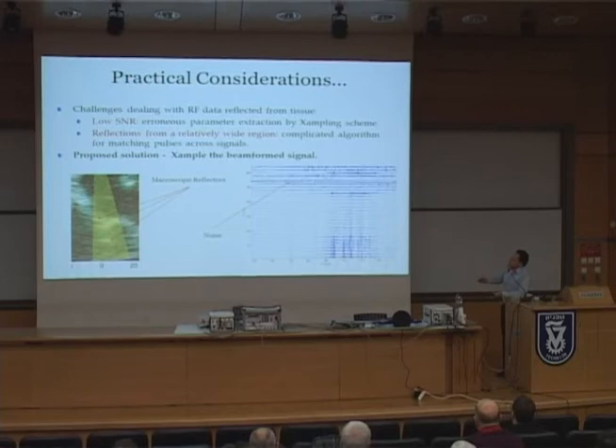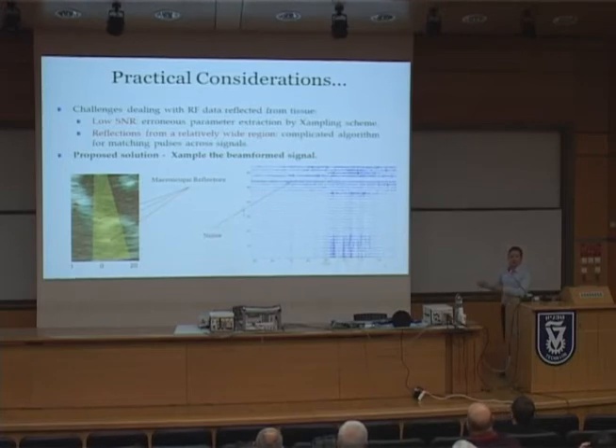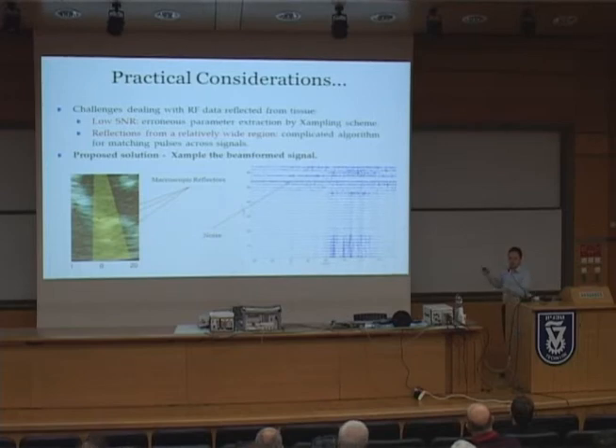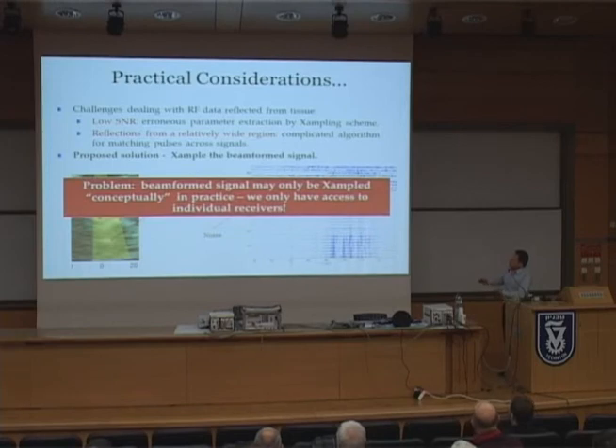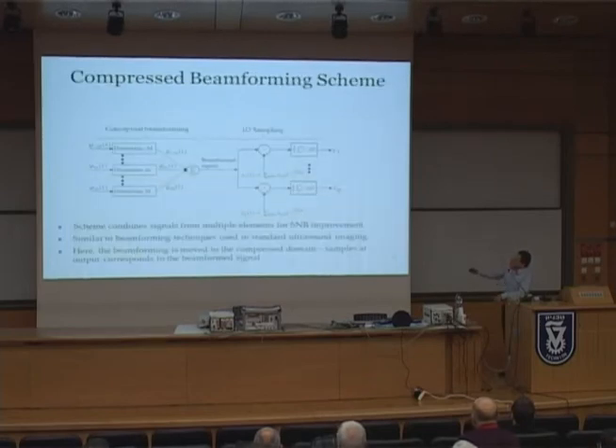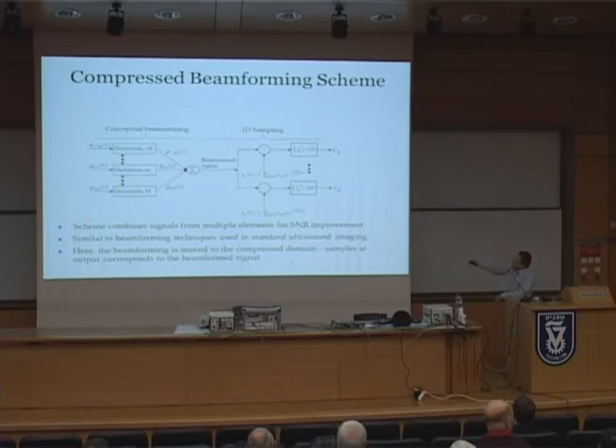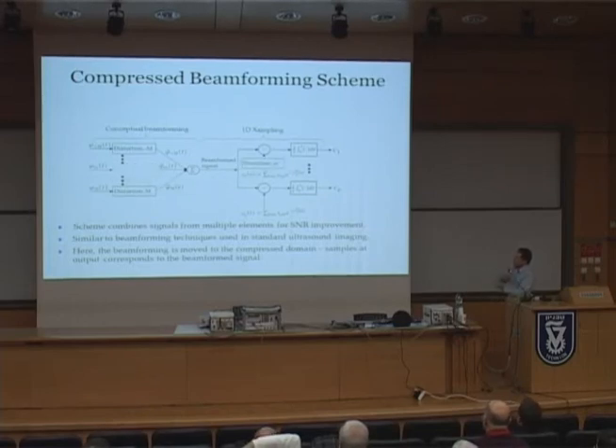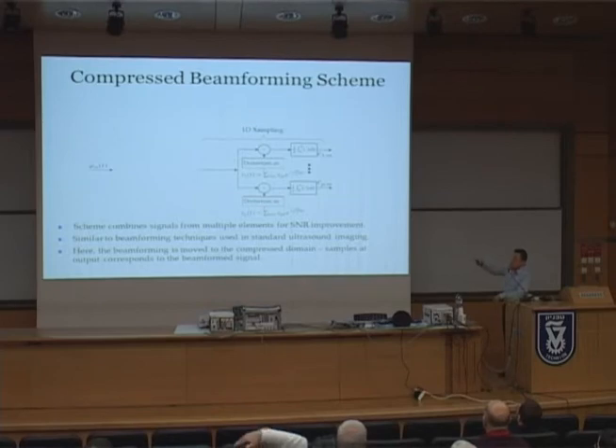Our proposed solution was to sample the beamformed signal. The only problem is that the beamformed signal does not exist in the analog domain — it is generated by ultrasound devices from the samples of the analog signals. Our idea to overcome this was to conceptually assume we could generate the beamformed signal in the analog domain, and then fit it into the one-dimensional multi-channel sampling scheme. We have the beamforming process which involves distortion, and by rearranging the processing blocks, we can show that we can switch this beamforming distortion with an equivalent distortion applied to the modulating kernels.